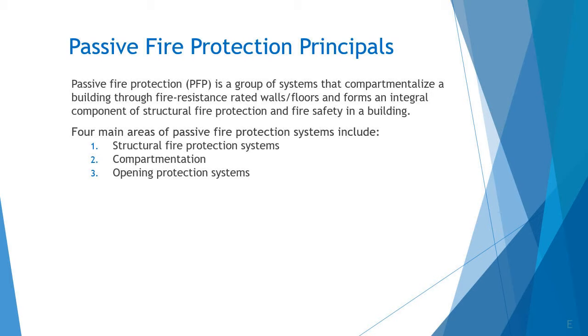Then opening protection - any elements passing through compartmentalized items, particularly firewalls and smoke walls, need to maintain their rating. If you've got a 2-hour constructed wall separating two spaces, and you punch a duct or conduit through it, you want to make sure it's still a 2-hour wall after that.